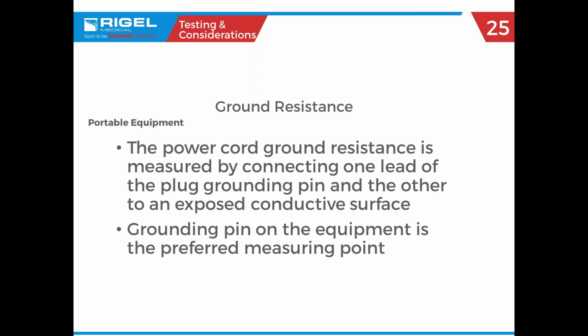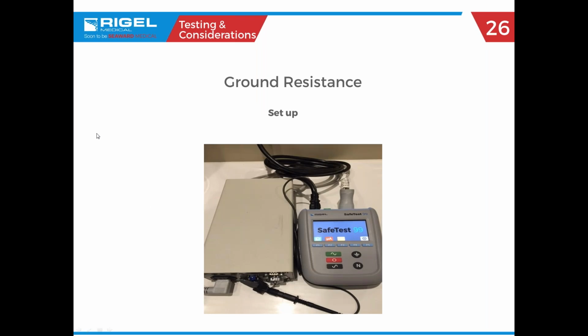Okay, so let's take a look at ground resistance, as that's what they want you to test first. Makes sense. To do this, you're just going to take your test lead, attach the alligator clip, making sure it's an exposed conductive surface on the device under test. Then you take the plug and plug that into the DUT socket on your safety analyzer. That's how you get your ground resistance. Very easy. You just have to make sure you have a good solid connection there, or you'll get some bad readings.